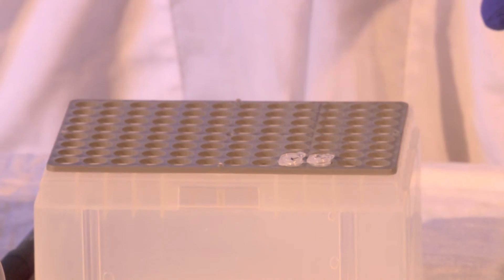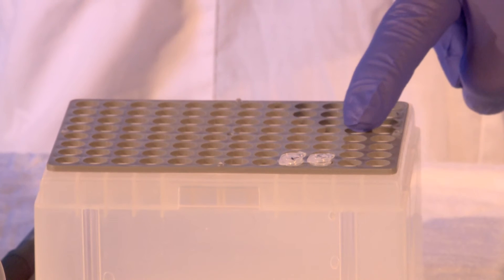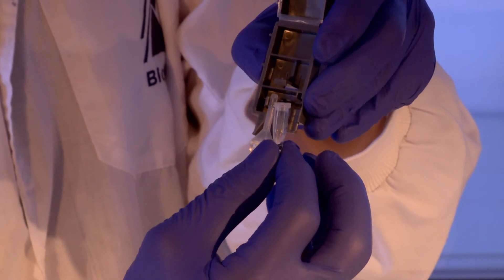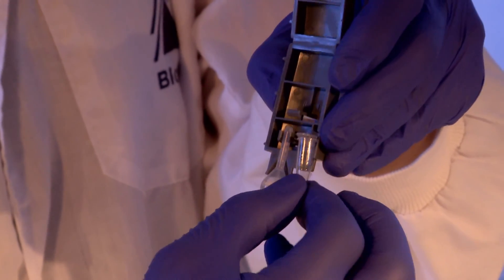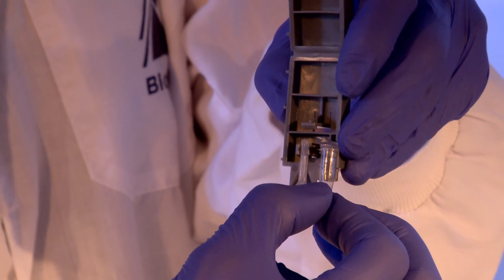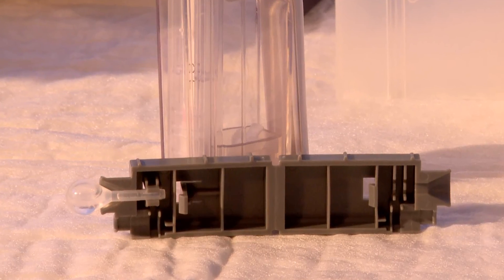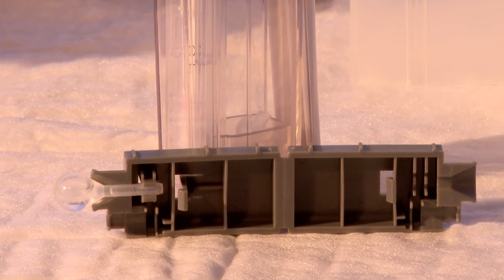At no stage of the process is it necessary to open the PC-RUN reaction tube. Mark each chamber with the sample ID. Align the lid section of the PC-RUN reaction tube with the wide partition located beside the buffer bulb. The lid of the tube has two protruding sections; these must be aligned with the inner section of the amplicon cartridge.